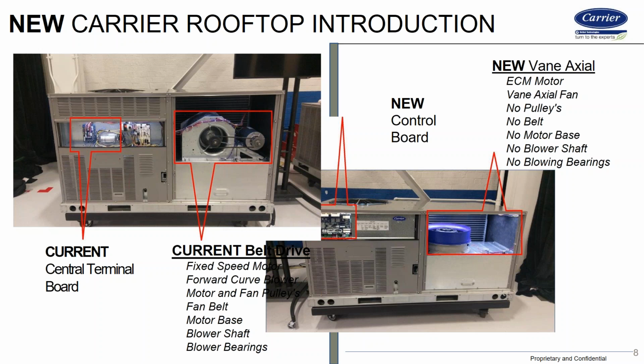It's not like a full variable speed motor, like we would have in a modulating furnace. If you're a Carrier guy, like a 59MN or a TN furnace, it doesn't do that torque calculation that those motors do. On the furnaces, every 100th of a second, it looks at the RPM of the motor and at the amp draw. Amp draw is converted into a torque value, and between those two numbers, it calculates what the external static pressure is, or what the change was that took place. This motor doesn't do that. This motor is more like the X13 type motor, or constant torque motor.